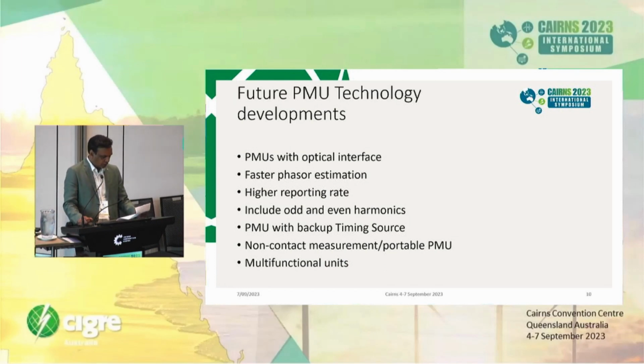In order to assess the operating condition of the grid in real time, predict behavior, and respond to events, a PMU should be capable of achieving fast and accurate measurements during transient conditions. Most commercially available PMUs are based on discrete Fourier transform with 2 to 6 cycles for phasor estimation. Their dynamic response is not accurate enough to capture system transients to initiate control actions to stabilize the grid. PMUs with adaptive window size technology and an instantaneous phasor estimation algorithm will enable transient capture and prediction.